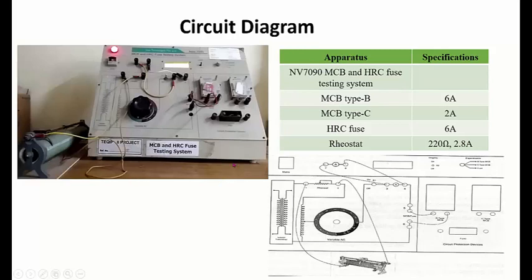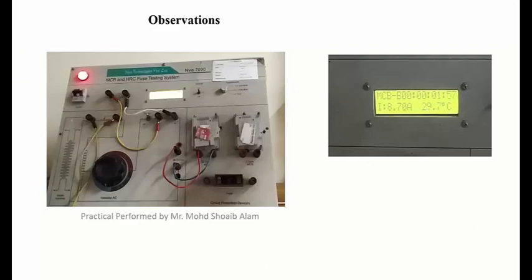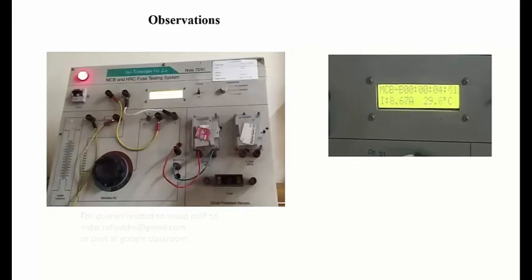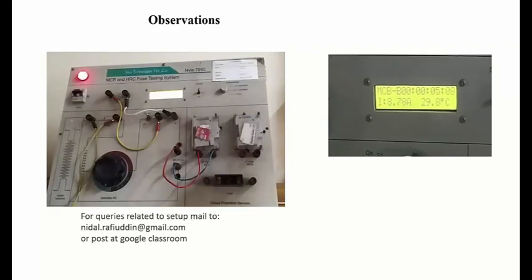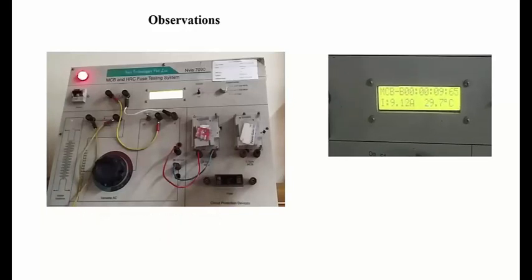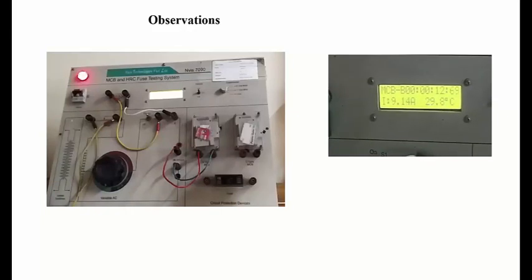Shown on the left side is the connection that had been done using the circuit diagram. We'll be performing experiment testing type B MCB. We'll be taking four readings starting from 8 ampere, then 9 ampere, and so on. Shown here is the test corresponding to current taken as 9 ampere.